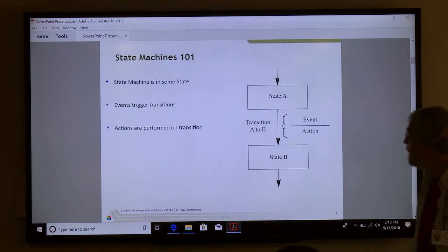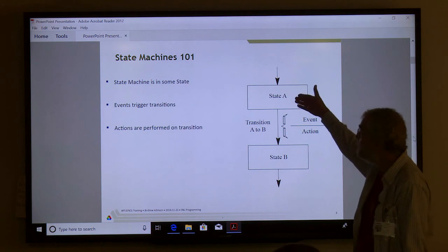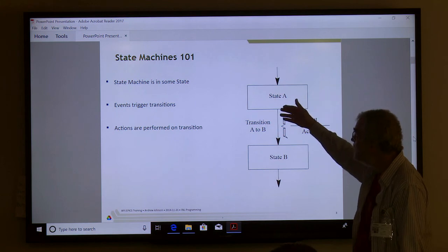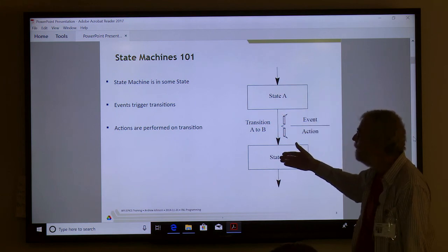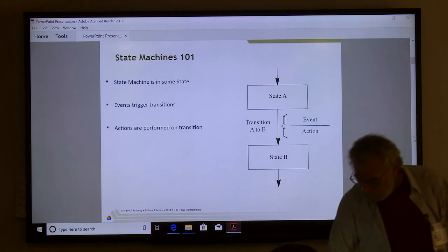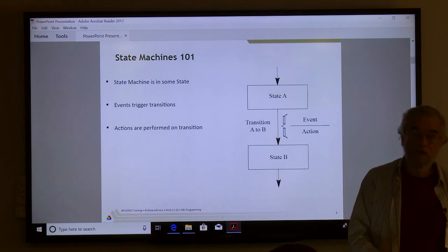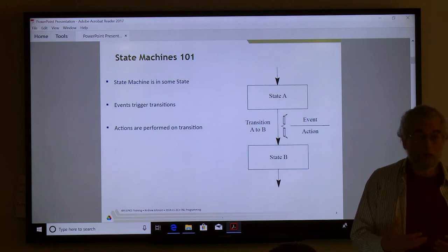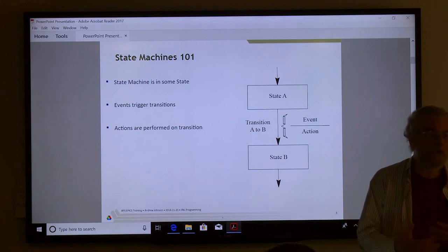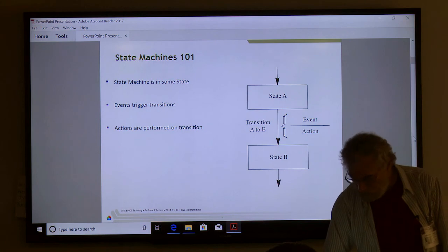It's intended for state machines where you can identify that you're in some state and where you can identify a transition, some event or action that takes you from state A to state B. But that's not the only kind of problem for which state notation language is used. It's also just handy because it's a nice way to write C code in the IOC and to write a channel access client in an IOC and not have to worry about all the channel access stuff. I mean, you're going to have to identify the PVs that you're talking to, but you don't have to go through putting monitors on and having callbacks. The sequencer does all that stuff for you.